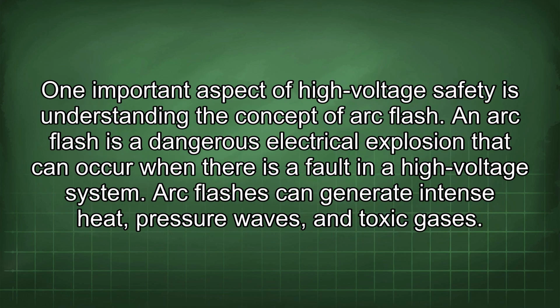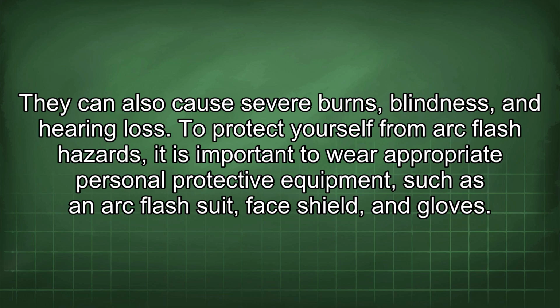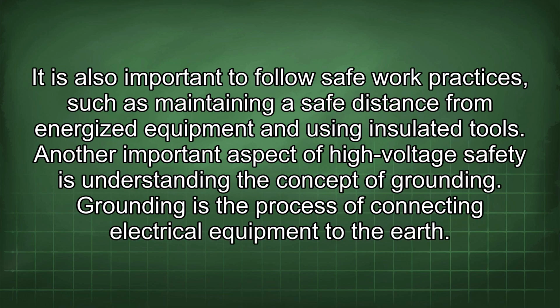One important aspect of high-voltage safety is understanding the concept of arc flash. An arc flash is a dangerous electrical explosion that can occur when there is a fault in a high-voltage system. Arc flashes can generate intense heat, pressure waves, and toxic gases. They can also cause severe burns, blindness, and hearing loss. To protect yourself from arc flash hazards, it is important to wear appropriate personal protective equipment, such as an arc flash suit, face shield, and gloves. It is also important to follow safe work practices, such as maintaining a safe distance from energized equipment and using insulated tools.